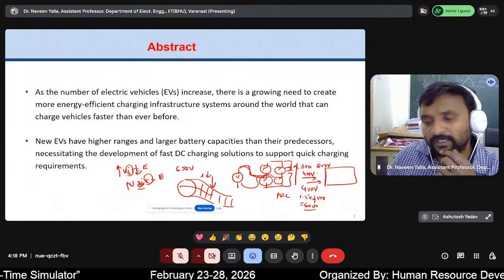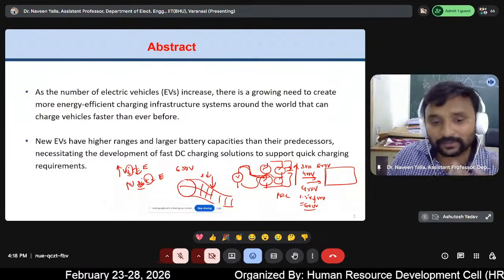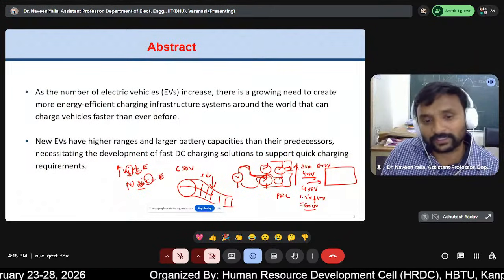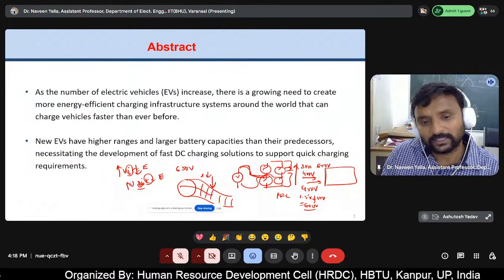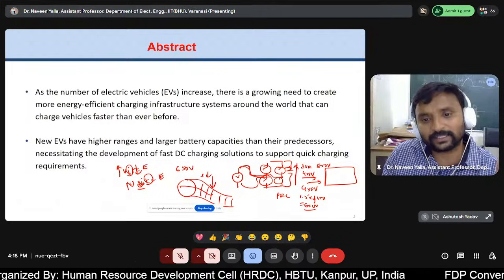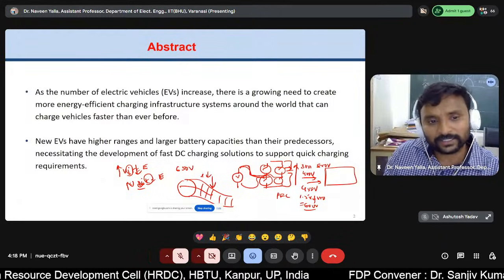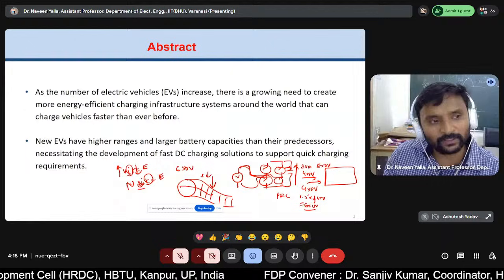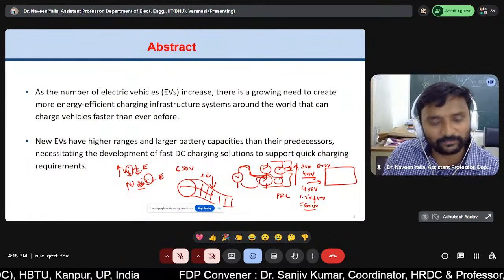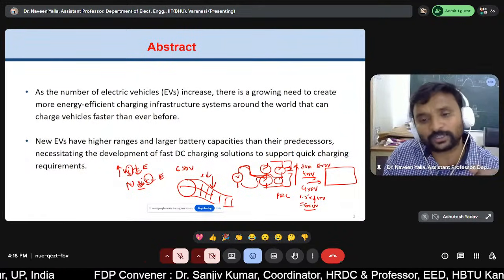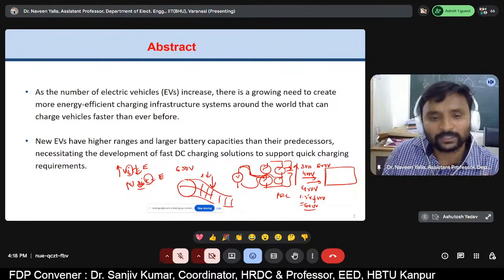And second, as I mentioned, specifically in mining - there are dumpers, big heavy trucks, and conveyor belts, all heavy machinery. The motor ratings, if you see, even in some specific heavy load cases, 11 kV machines are being used. How can you control that? It comes down to the drive, at the end of the day.